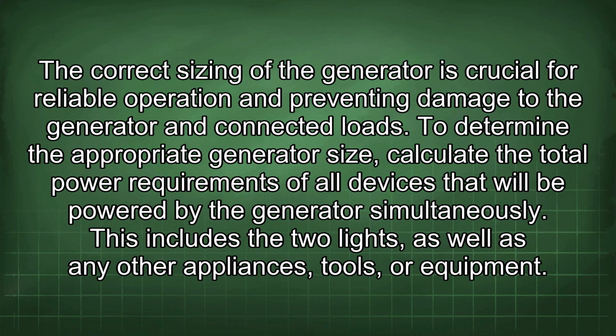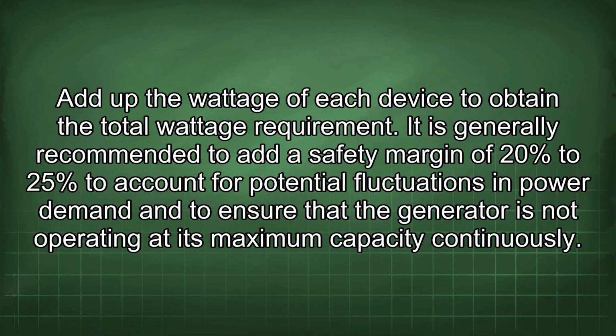The correct sizing of the generator is crucial for reliable operation and preventing damage to the generator and connected loads. To determine the appropriate generator size, calculate the total power requirements of all devices that will be powered by the generator simultaneously. This includes the two lights, as well as any other appliances, tools, or equipment. Add up the wattage of each device to obtain the total wattage requirement.